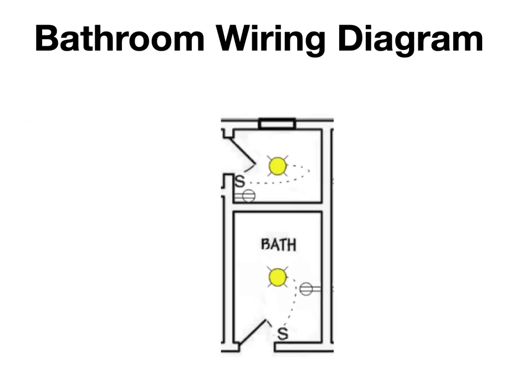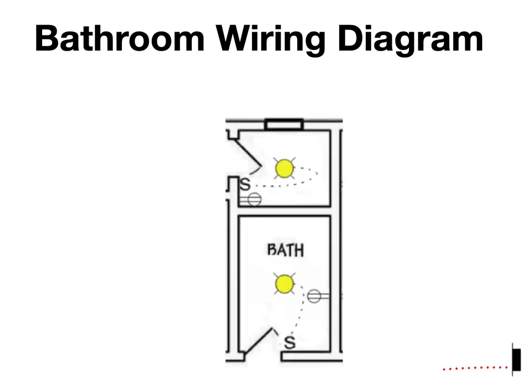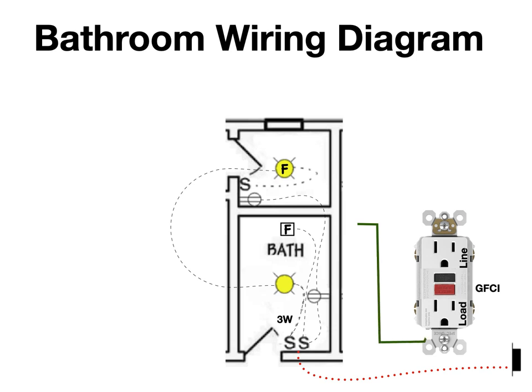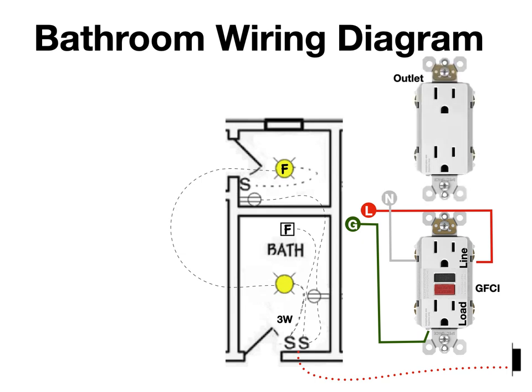Now we will look at the bathroom wiring in more detail. A third feeder wire is brought in from the power panel in the garage and connected to the switch box in the main bathroom. We want to add exhaust fans in both bathrooms. For the small bathroom it will be in the light fixture and will come on with the light, but in the main bathroom we want a separate fan controlled independently from a second switch. We will use a number 14-3 cable from the switch to the main bathroom light in order to carry on a power feed to the smaller bathroom. Power is fed from the two-gang switch box to the duplex outlet receptacles in the bathrooms. The duplex plug in the main bathroom is a GFCI (ground fault circuit interrupting) receptacle, which is a code requirement. The receptacle in the smaller bathroom is not required to be a GFCI if it is fed from the load side of the main bathroom receptacle.